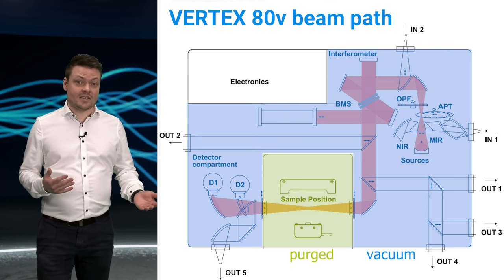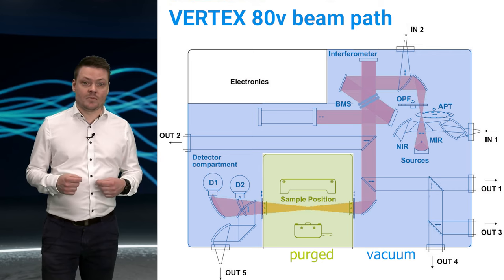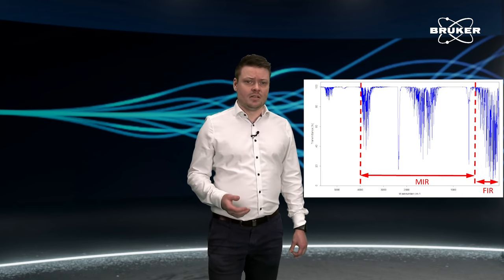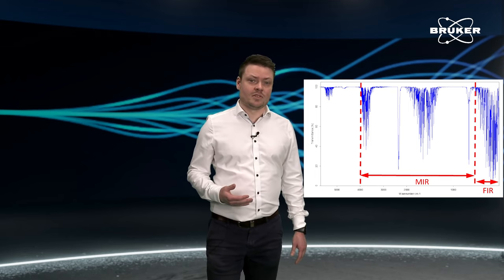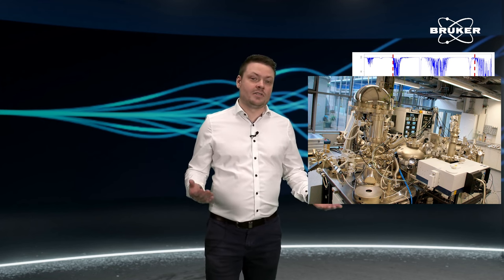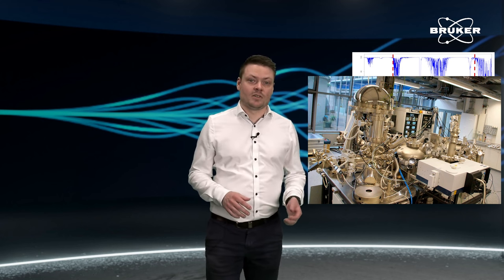Aggregation studies can also last very long, and there the very stable background conditions of a vacuum system come into play. When you're working in the far infrared or even the terahertz region, you're dealing with small signals and strong water absorption. Here, a vacuum system can offer significant improvements. Also, if you want to connect your FTIR spectrometer to an ultra-high vacuum system, it makes a lot more sense to also have your FTIR spectrometer under vacuum conditions.